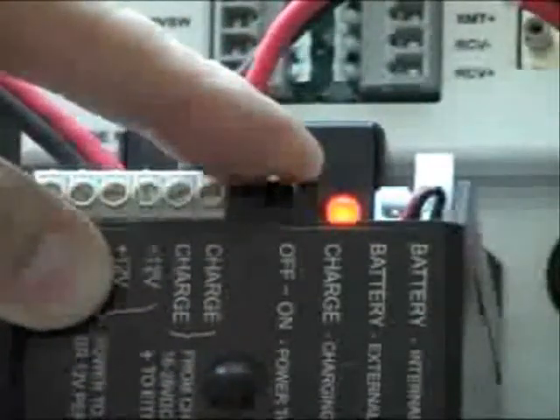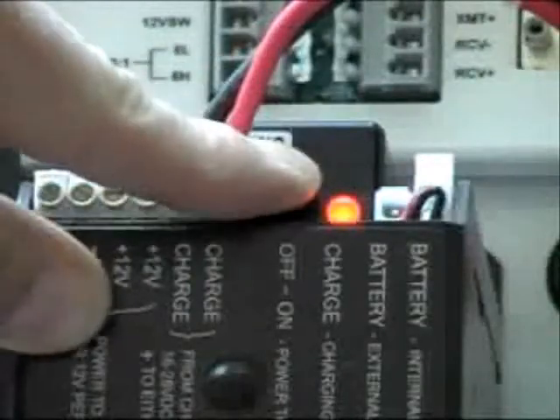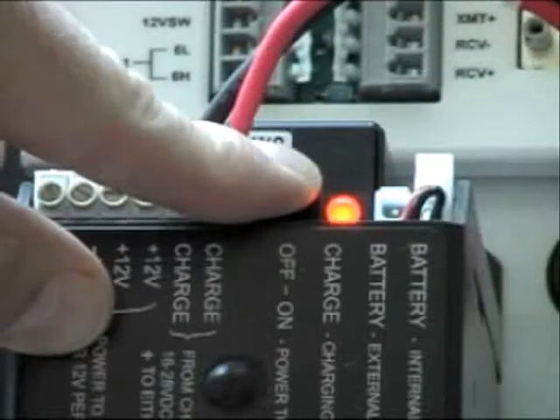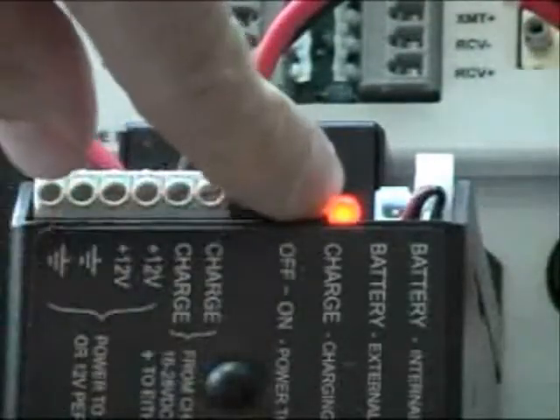Newer weather stations look like this one. They have a black PS100 in the same location as the white battery bracket on the older style stations. These have a connector on the back of the enclosure. The PS100 has a red LED that indicates charging voltage. It does not indicate on or off. The PS100 has an on-off switch and the down position is on.